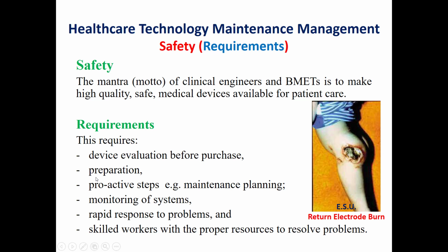Another requirement is the preparation for the use of this medical device in the healthcare setting through training for the staff in the proper and safe use of this medical device. Another requirement is proactive steps such as the determination of the inclusion or exclusion of this device from the preventive maintenance program. Another requirement is the monitoring of systems.